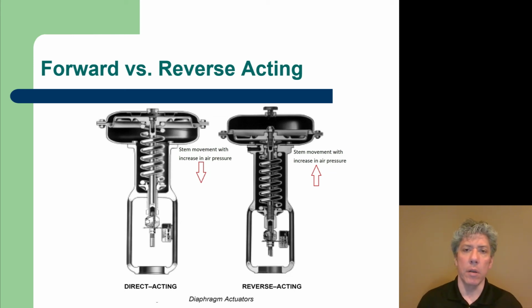Now there are also forward and reverse acting actuators. The one on the left is the one we've been looking at so far, with air coming in the top and the bottom of the spring grounded. This is direct acting because as you increase the pressure on top of the diaphragm, the stem of the valve is pushed farther into the valve body. Both of these are considered forward motions or increasing, and so this is direct acting.